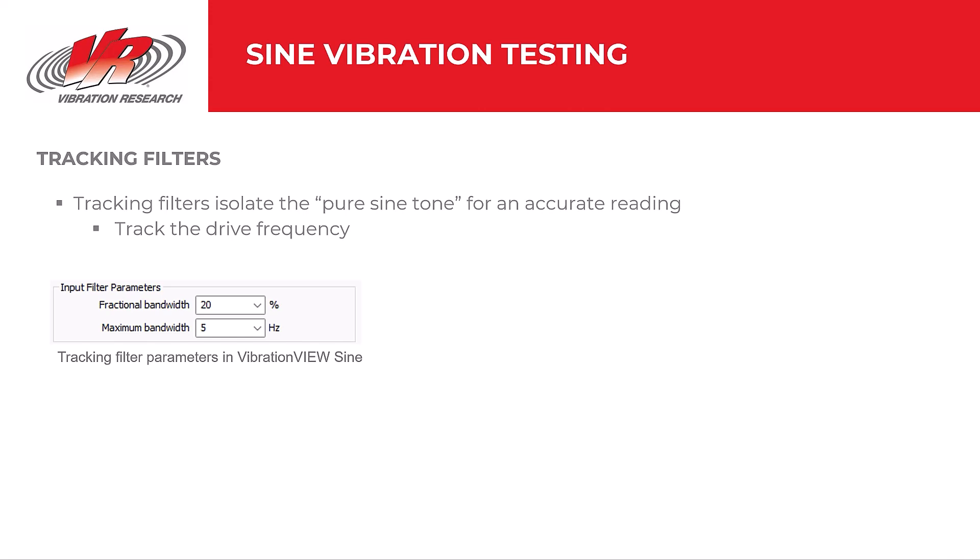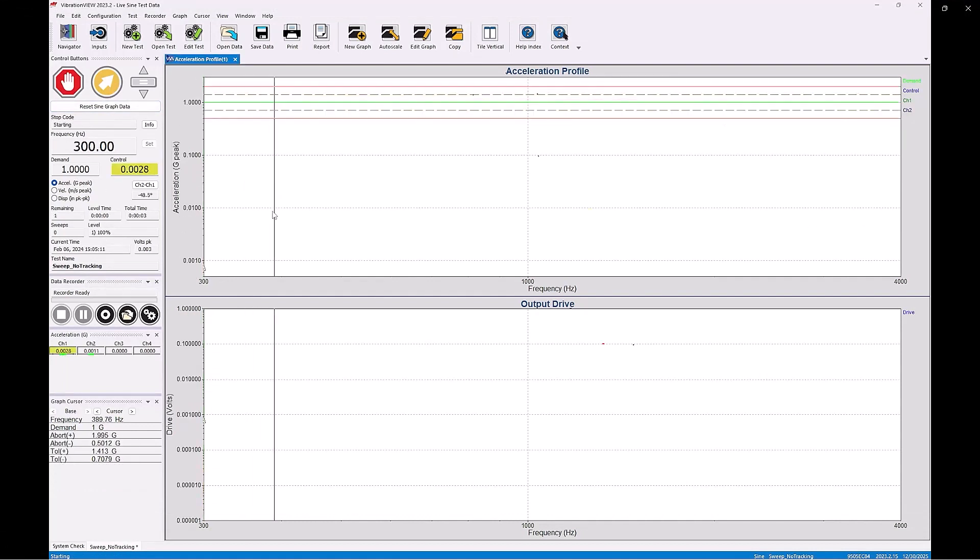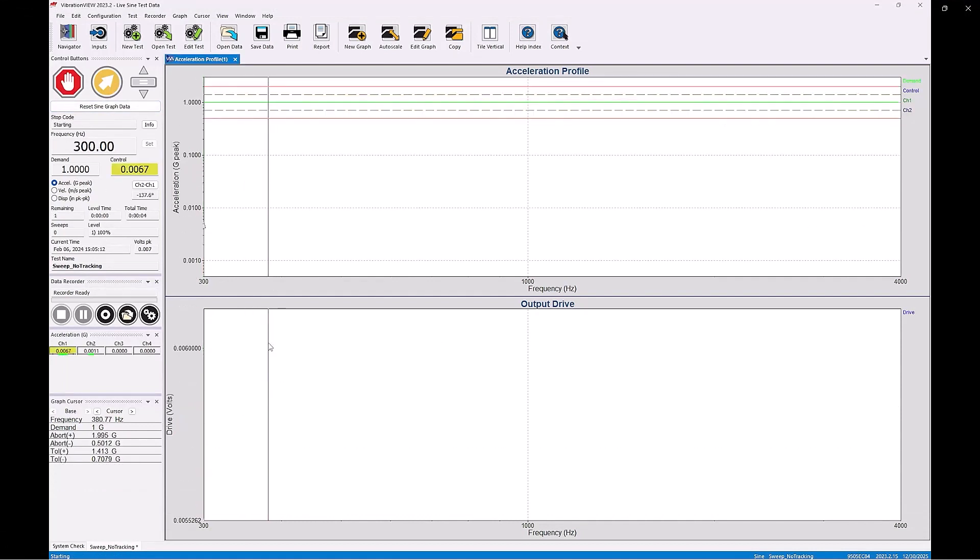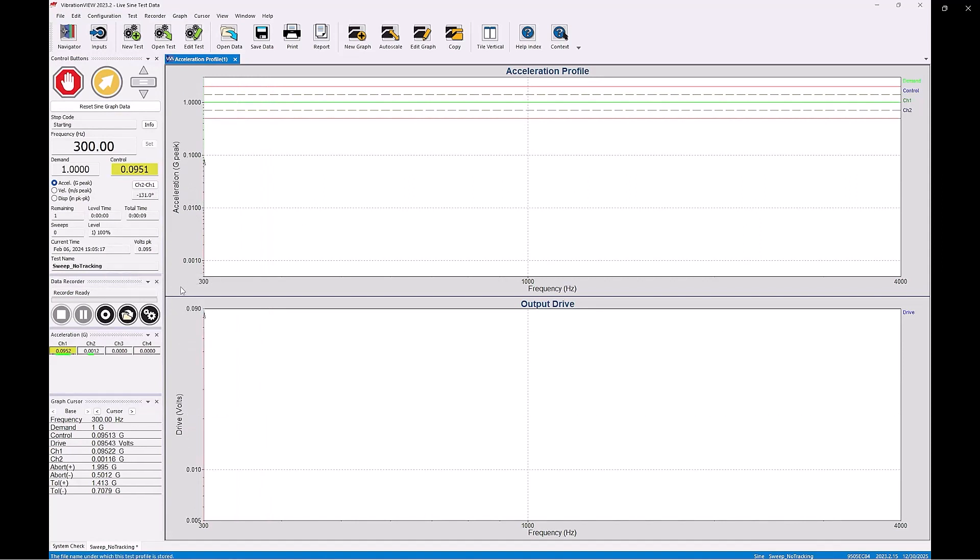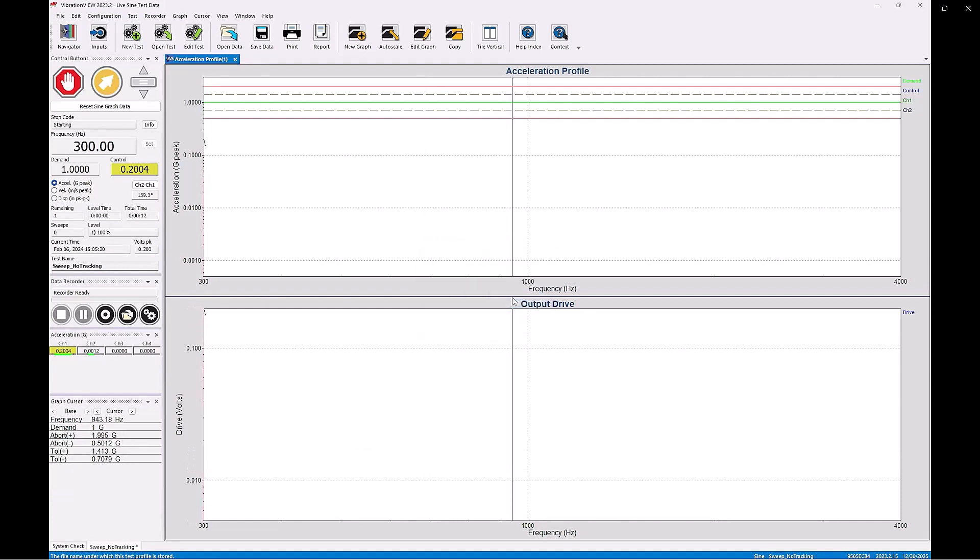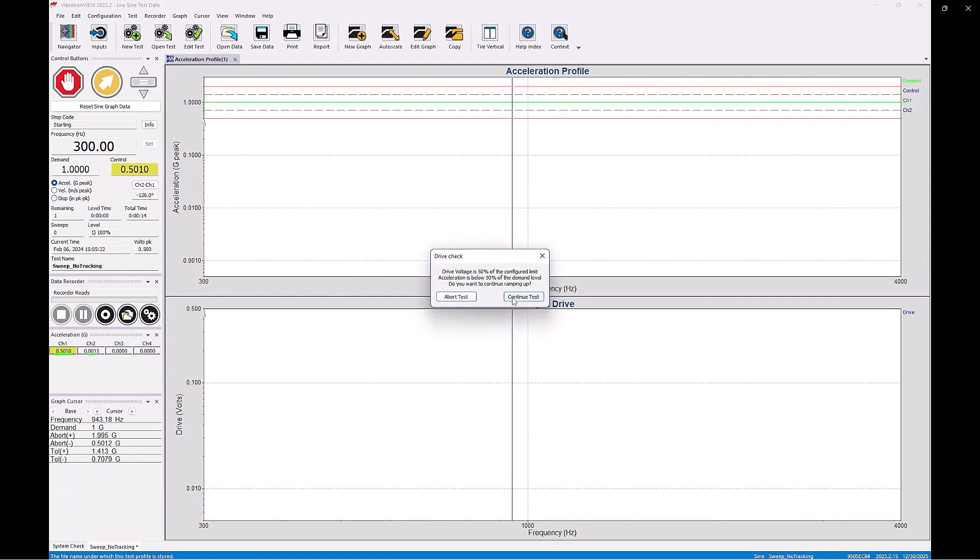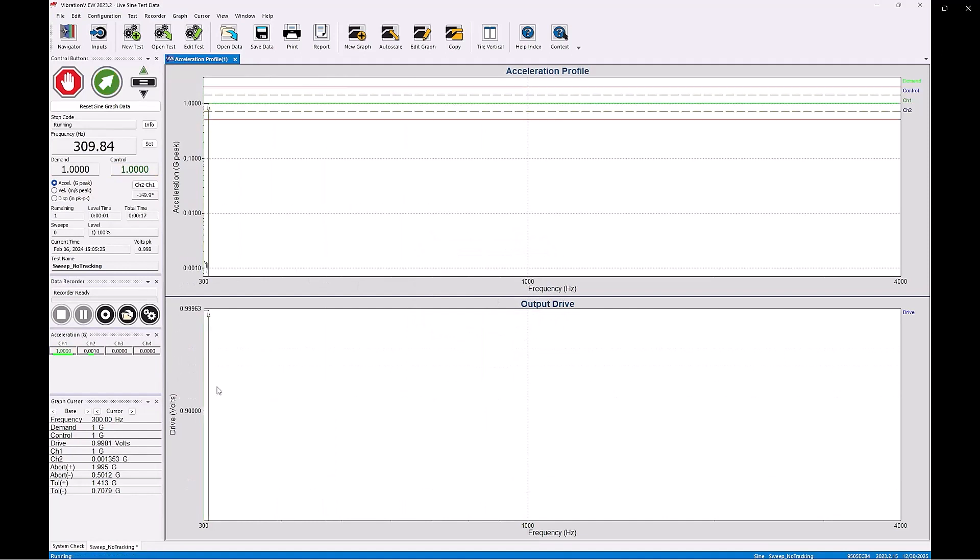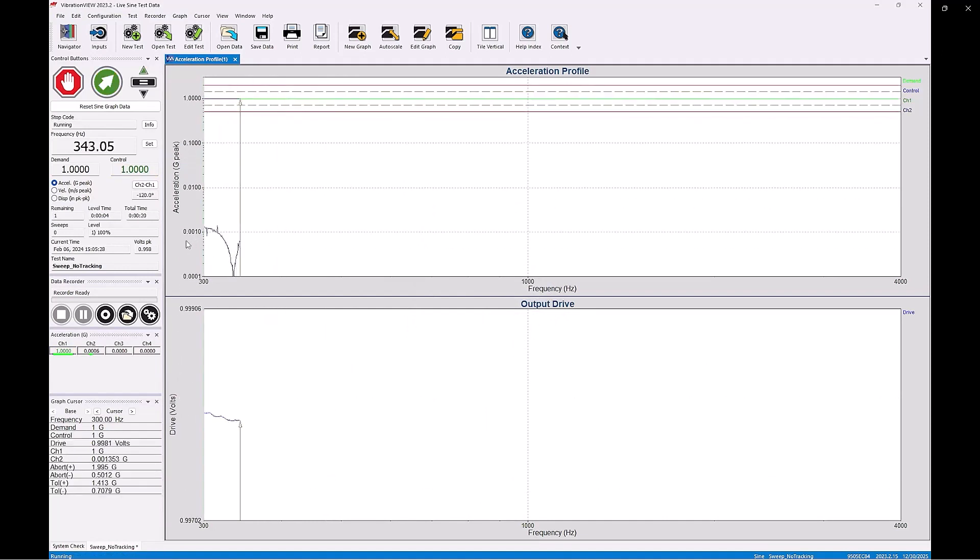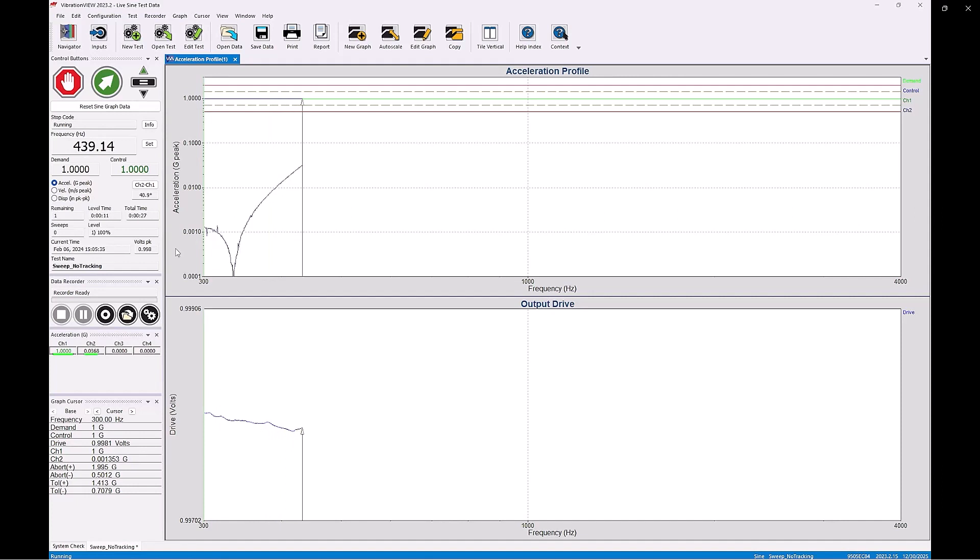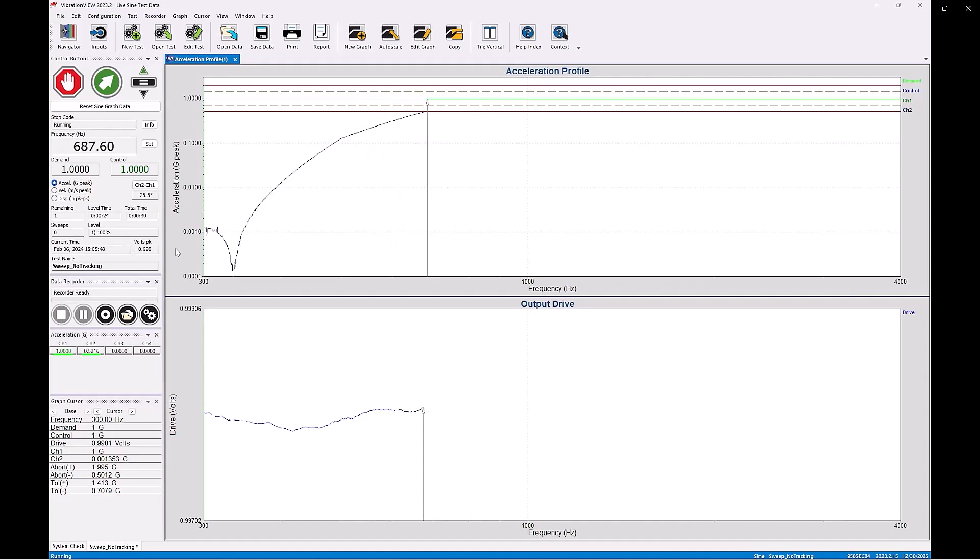Let's move to vibration view for an example. As an example, let's set up a sine sweep from 300 Hz to 4000 Hz at 1 G. On the controller, I looped the output to the input on channel 1. I also used the observer as a function generator to generate a 1000 Hz wave at 1 G and fed it into input channel 2. Without a tracking filter, the controller reads the acceleration at all frequencies from 300 to 4,000 Hz and controls based on the average RMS. We can see that that 1000 Hz noise will contribute to the average RMS and at some points may affect the control reading.